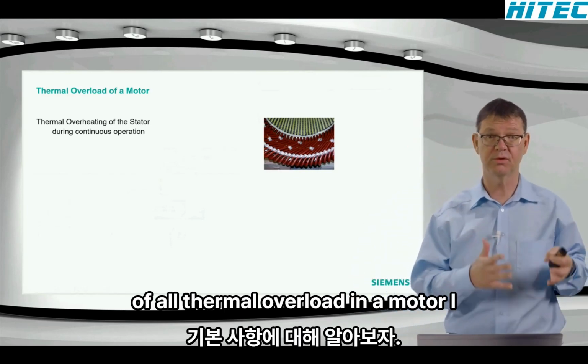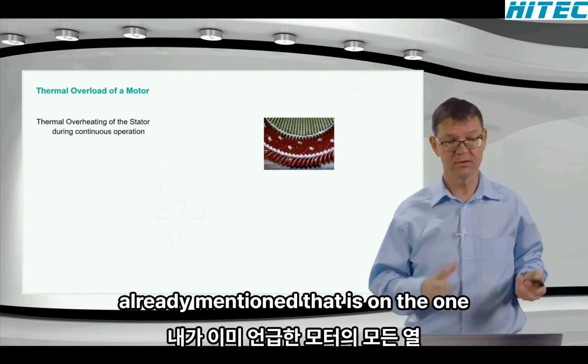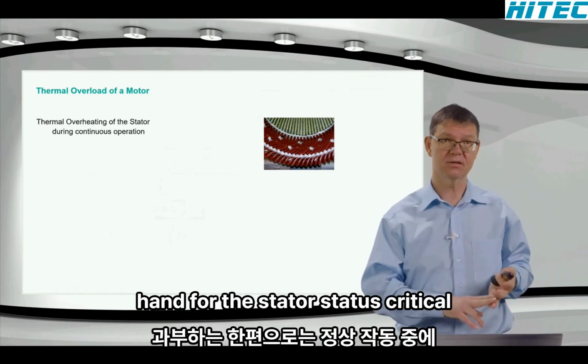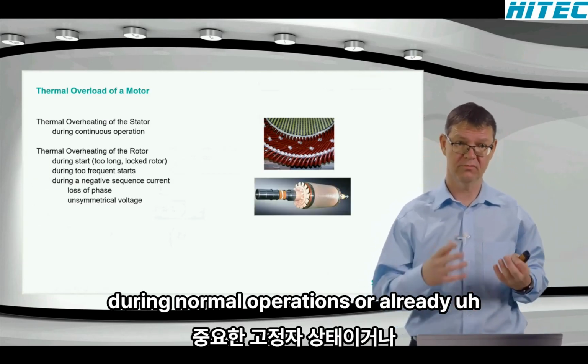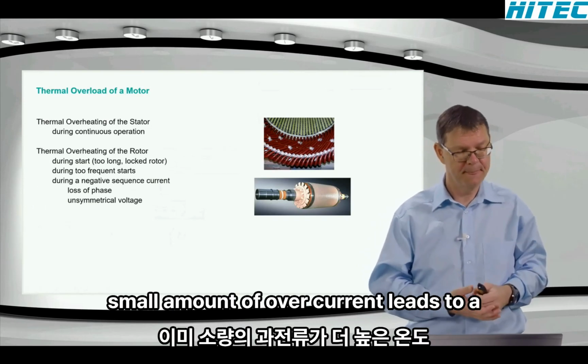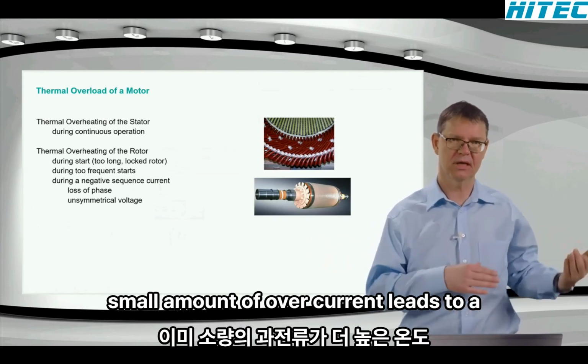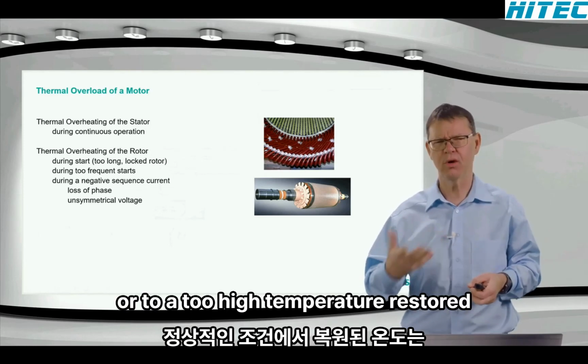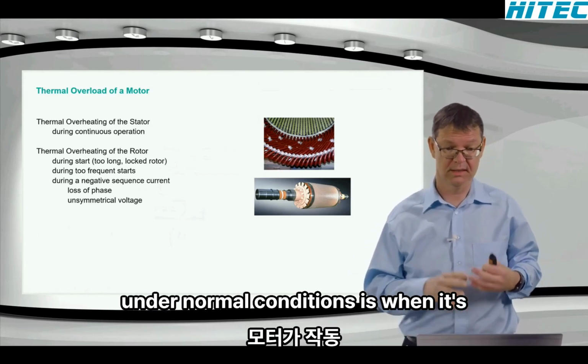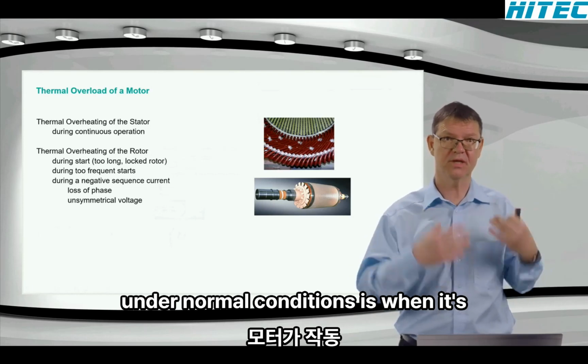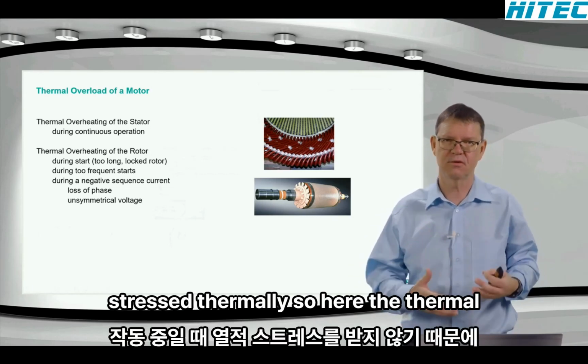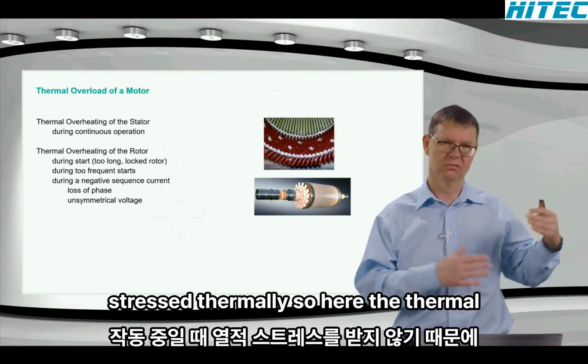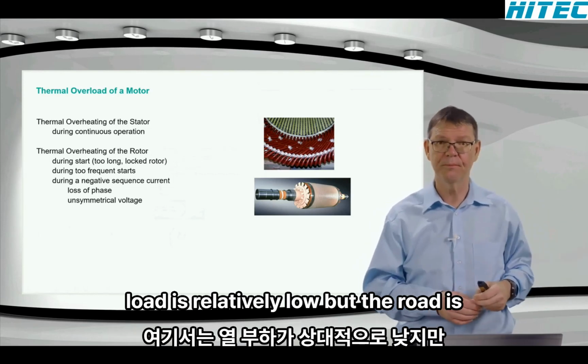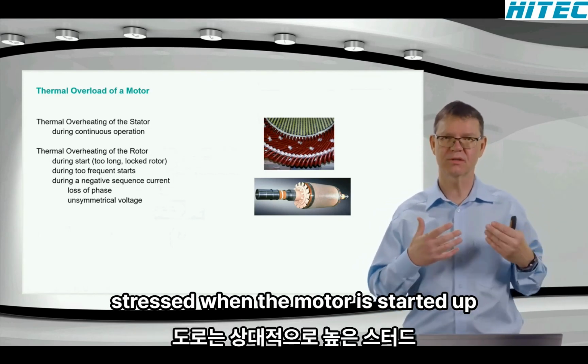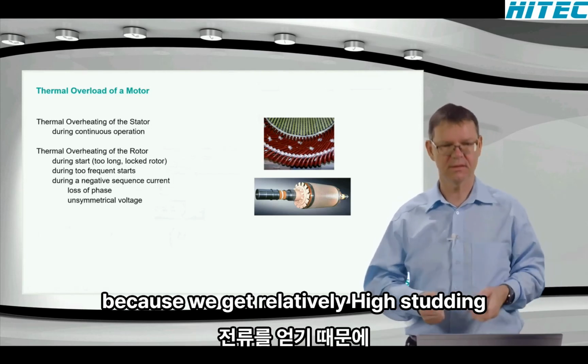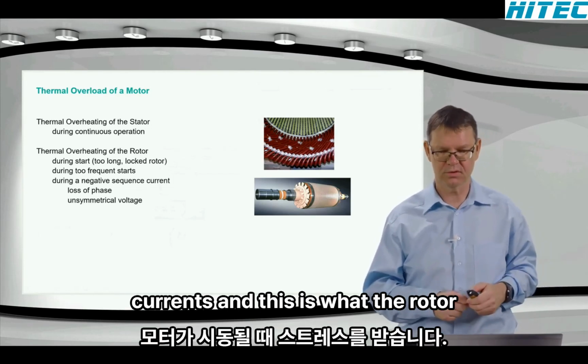First of all, thermal overload in a motor, I already mentioned that, is on the one hand for the stator. The stator is critical during normal operation, so already a small amount of overcurrent leads to a too high temperature. Whereas the rotor, when the motor is running, is not stressed thermally. So here the thermal load is relatively low.